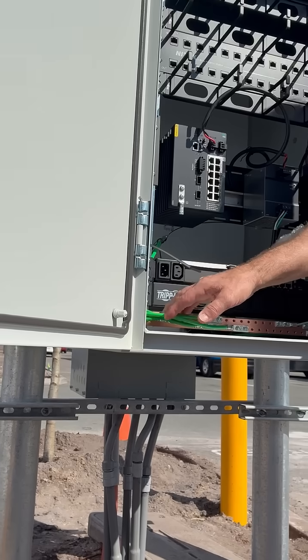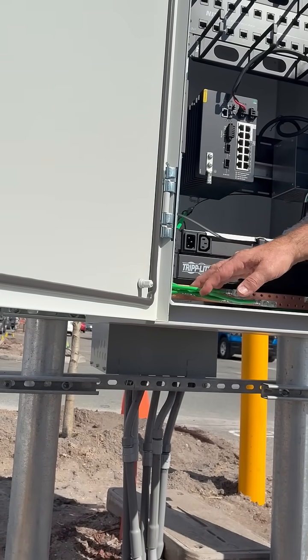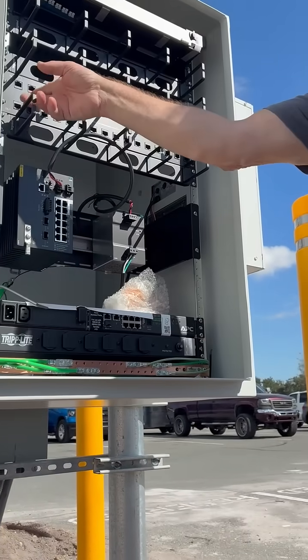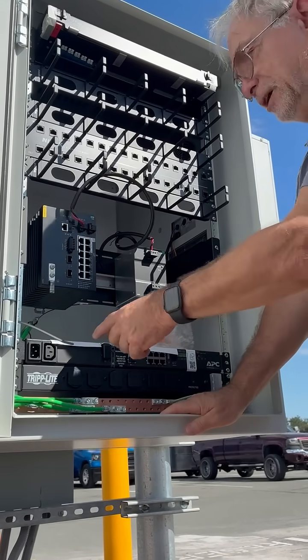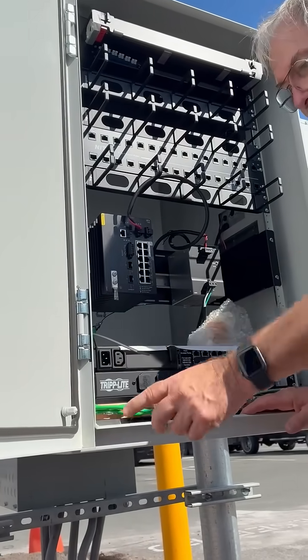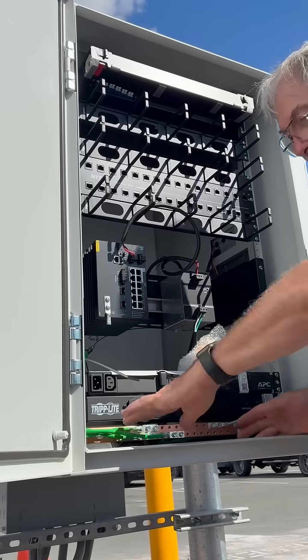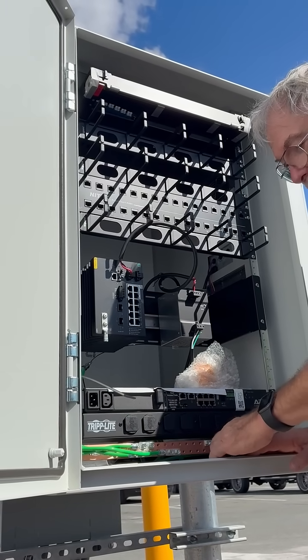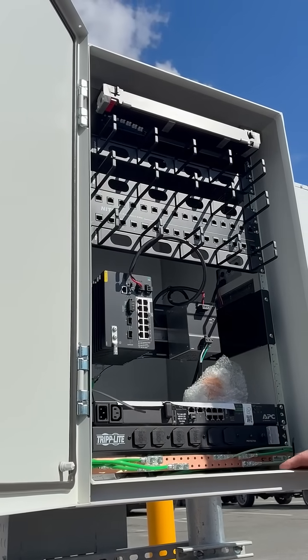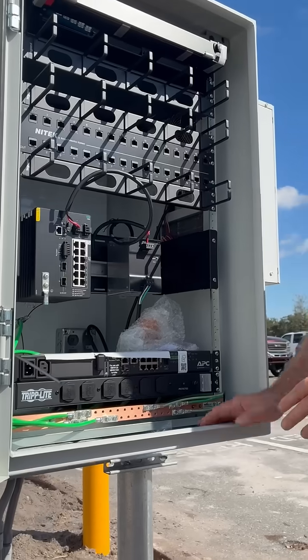Hold on — number six, yes. You're gonna take one of those and run it to the grounding stud on the back of the Nitek. You're gonna take a number 10 and run it over to the door. If it means moving this over here, this should actually be reversed — or just run it along the bottom and pick it up. Leave enough slack for the door to open.